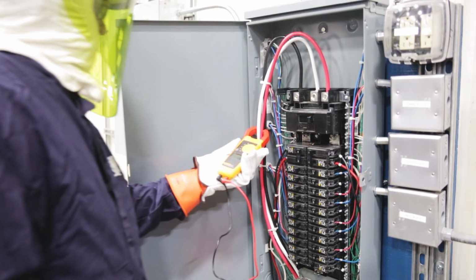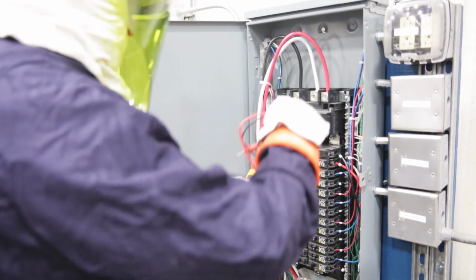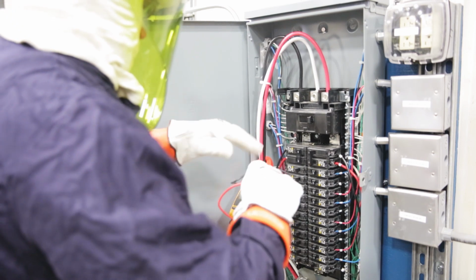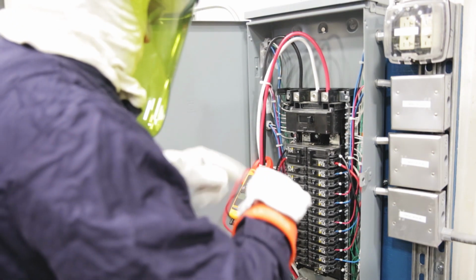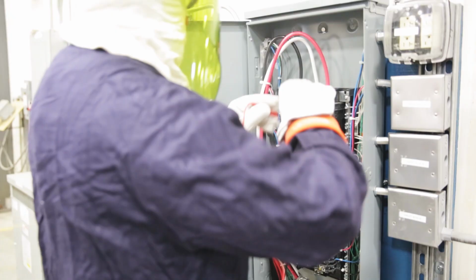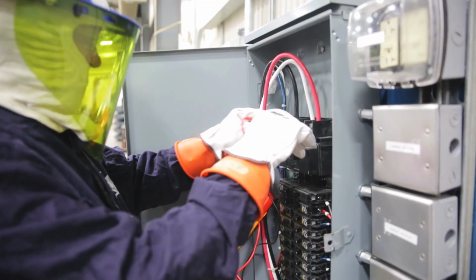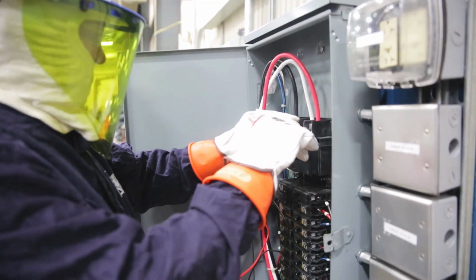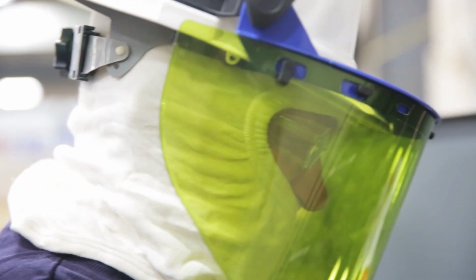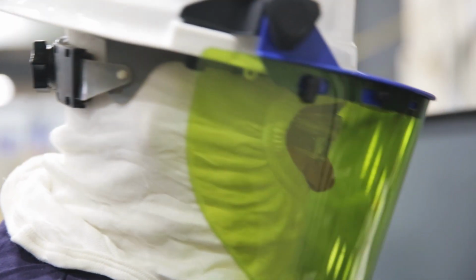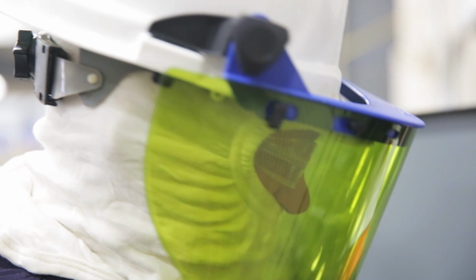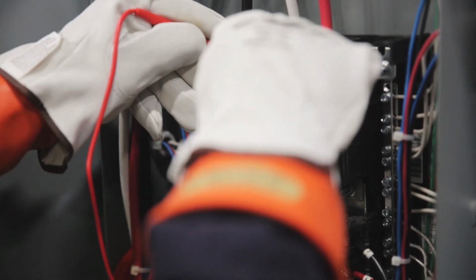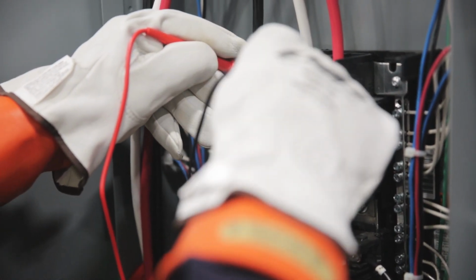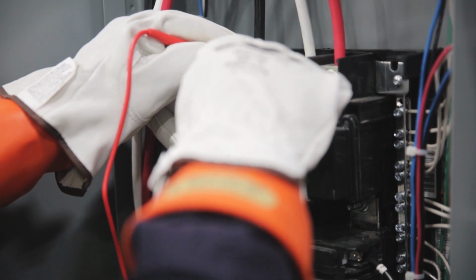More commonly at Southern Air, electricians and service technicians are potentially exposed to arc flash hazards when troubleshooting electrical issues in the energized state. Once issues are identified, the energy source must be de-energized and isolated for repair work to be conducted. Additional training is required to troubleshoot or perform work on any circuit greater than 50 volts. This requires arc flash training and special PPE requirements and permits.